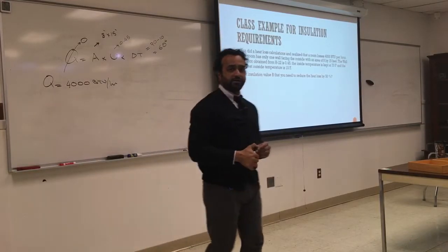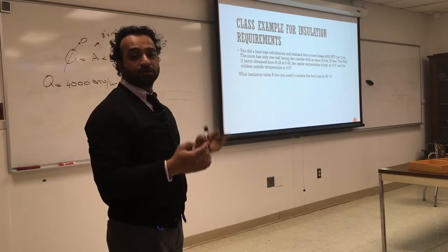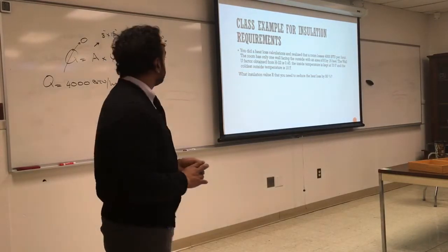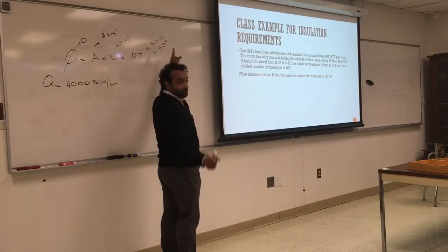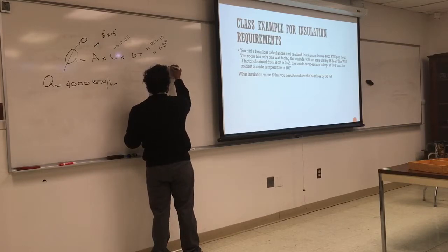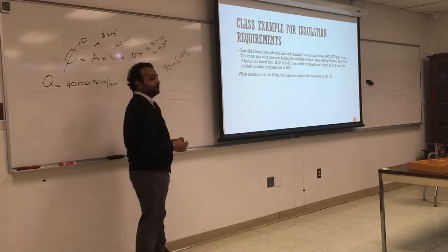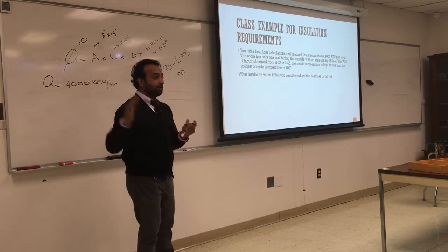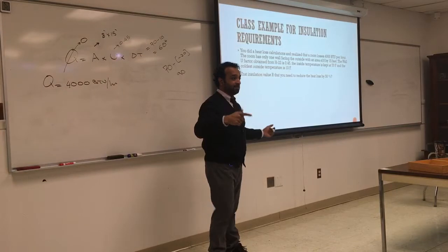Quick question. What if you get a negative number as the delta T? You flip it. The delta T is the higher minus the colder. Good question. So let's say that the inside is 70 and the outside is minus 20. So that will be 90. Because you're going to go 70 all the way to 0, then another 20, so the difference between them is 90. Make sense?